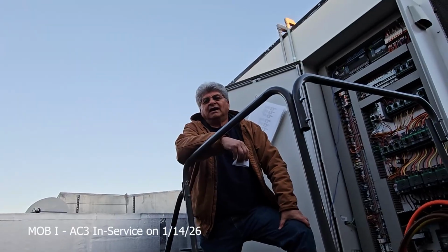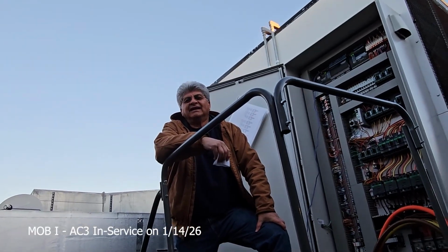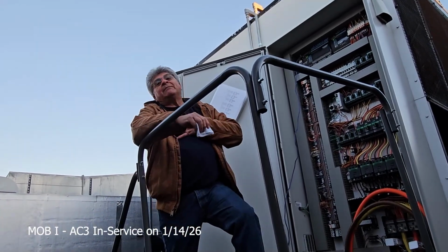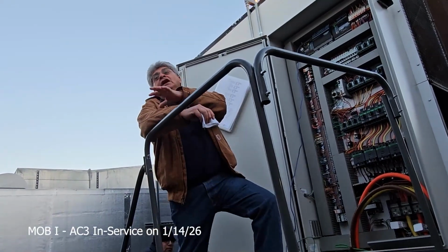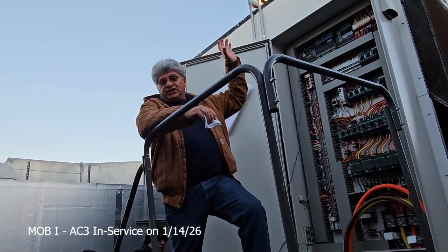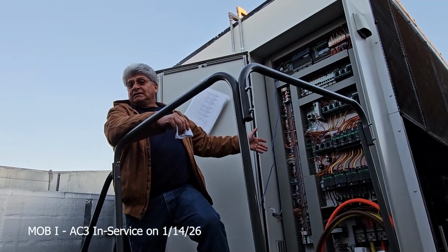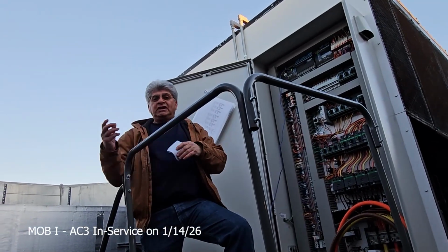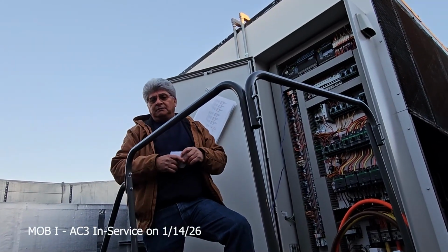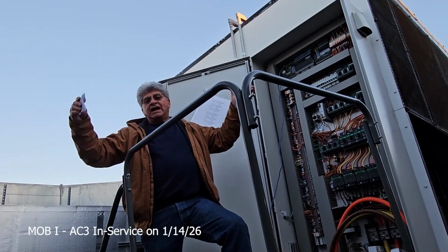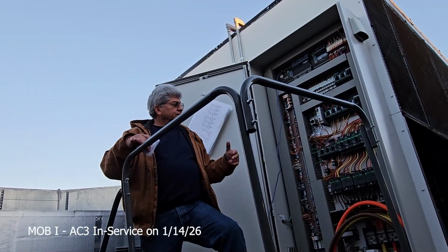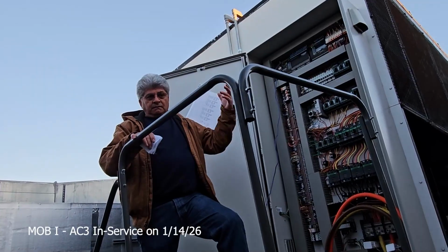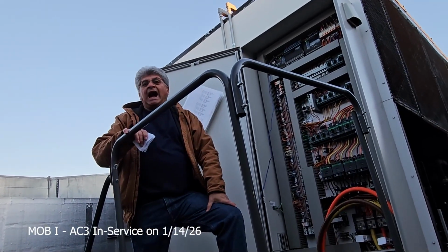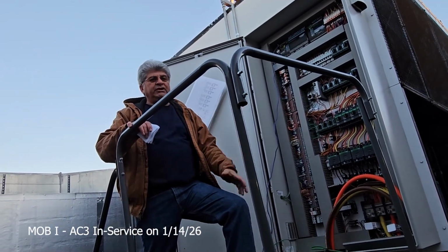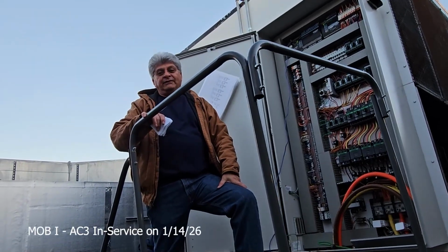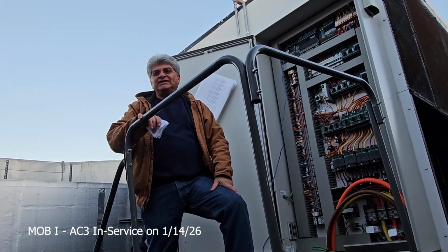Some of our units are Delta P high. They won't allow us to run. That's not my call. No, I'm just asking. So yeah, in your environment, somebody made that decision whether they want the unit to stay running, annunciate, and let you know downstairs, hey, we got a filter trip alarm, our static's on the high side, and the unit needs maintenance. Okay. I doubt it, because I've seen them pretty dirty. I've changed them 3 times.